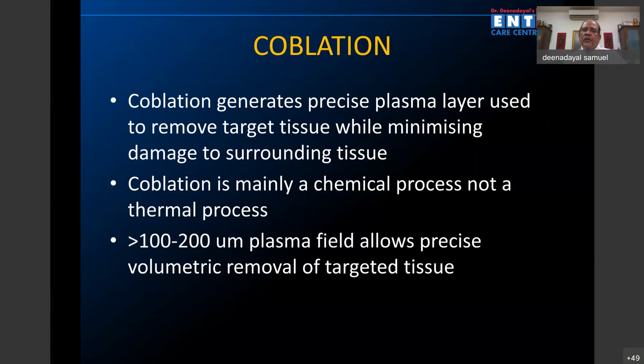What happens in coblation is that whenever electricity passes, it changes into radio frequency waves which, when mixed with saline, creates a plasma field. This plasma field, wherever you apply it to a target tissue, cuts through and can even vaporize that particular part. It is not a thermal process but a chemical process.